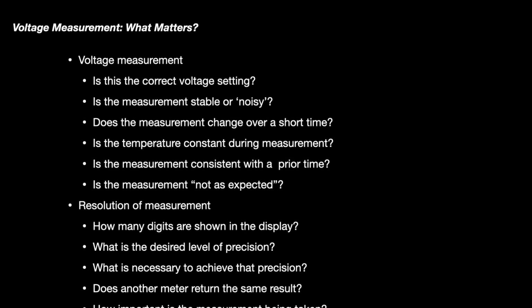Besides checking continuity, the most frequent measurement made by a multimeter is voltage. So what really matters when you're measuring voltage? Well, the big one is being on the correct voltage setting. There's a difference between measuring 1 volt on a 10-volt scale and measuring 1 volt on a 1-volt scale. Clearly, the meter is optimized to provide the best coverage for a given voltage within the scale that it operates. You should take note of whether the measurement indicated on your digital multimeter is stable or whether the last few digits are flipping all over the place. That's noise.